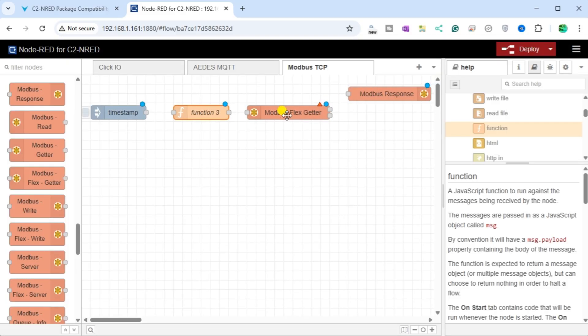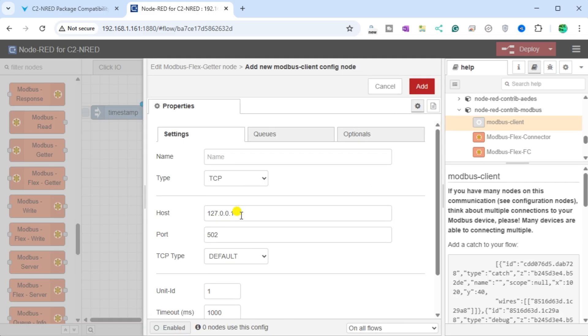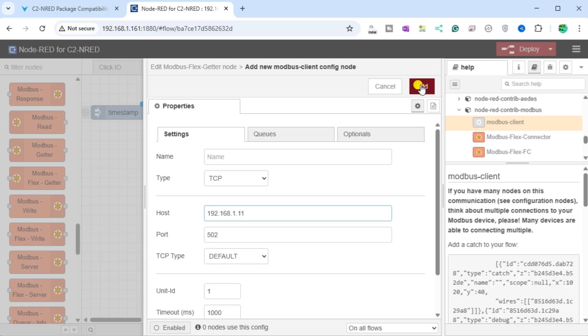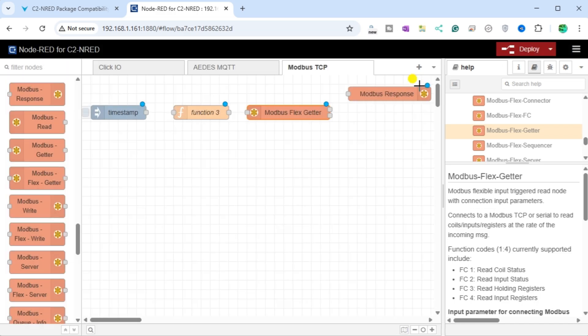The red triangle on the Modbus FlexGetter node means we must set up this node or provide additional information. Double-click on the node — the red box indicates we must set up the Modbus client so it knows where to send the instructions set in the Function node. Add a new Modbus client. Our type will be TCP and the host will be the IP address for the BRX DoMore PLC. Our port will be set to 502, which is the default. All other settings will be left as their default. Select Add. Our Modbus FlexGetter node is now set to communicate with our BRX DoMore PLC. Select Done.